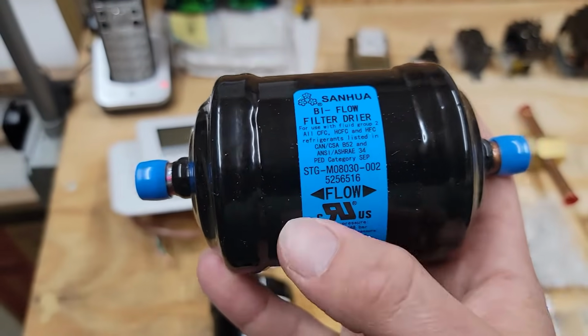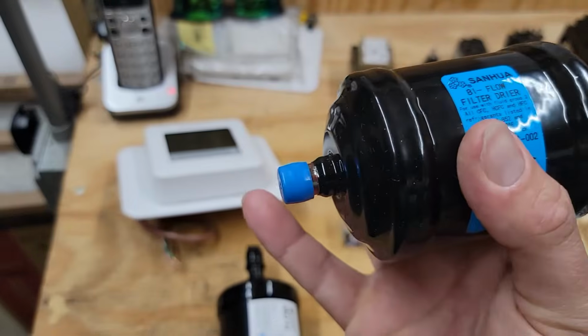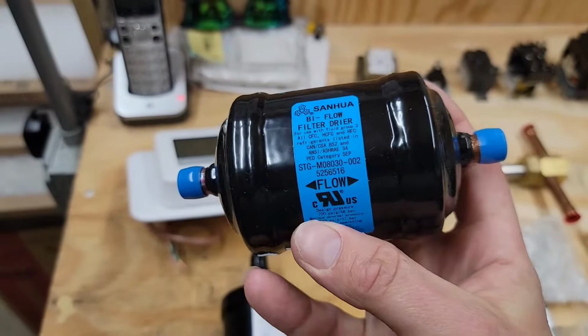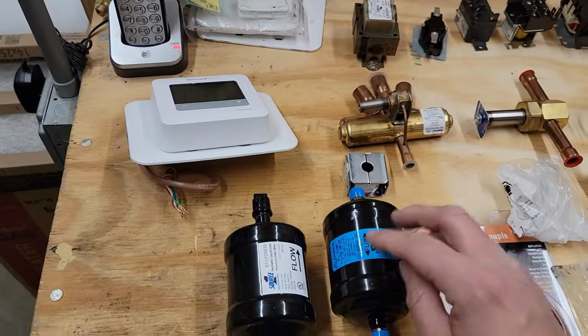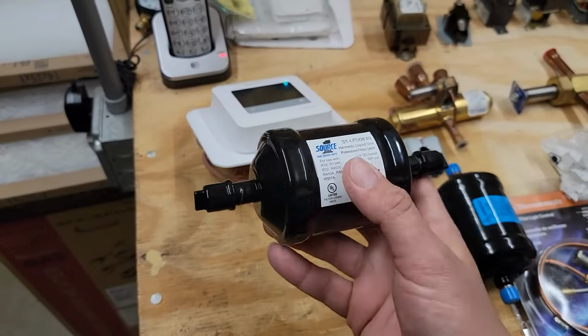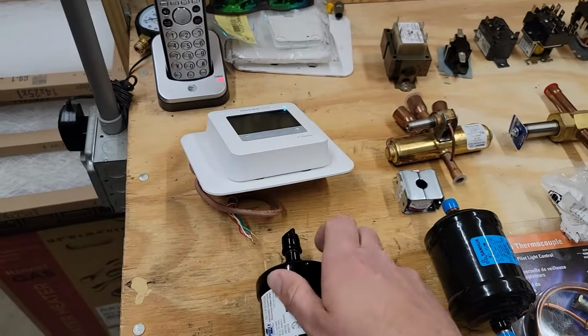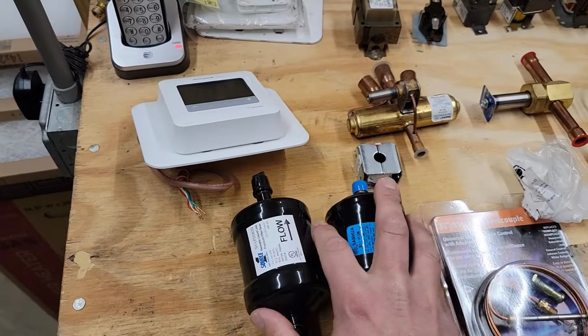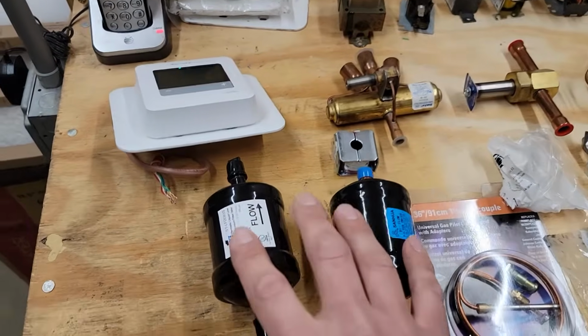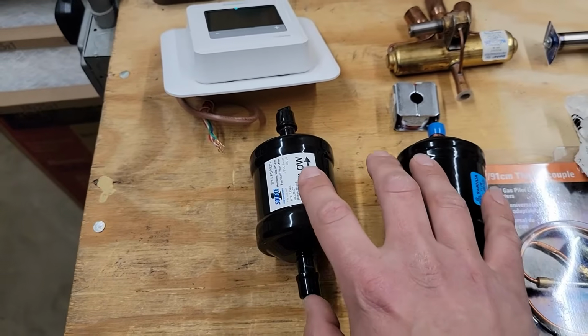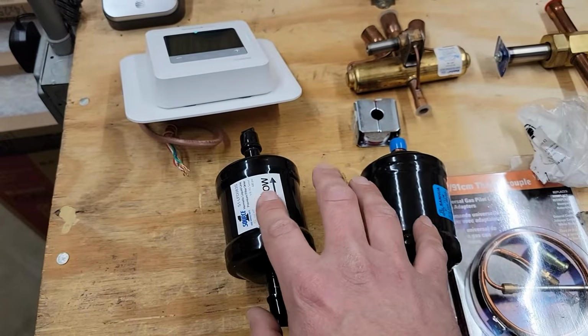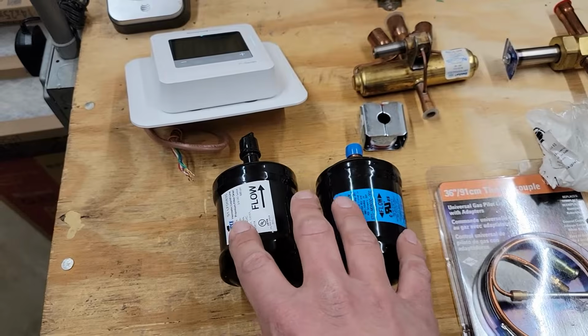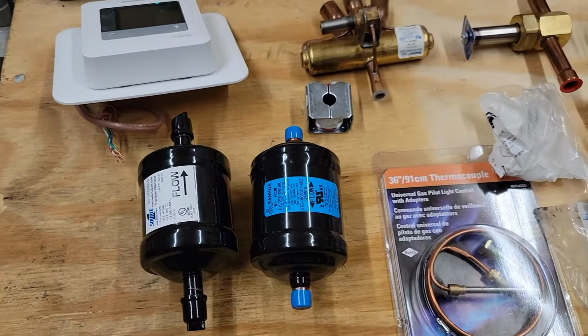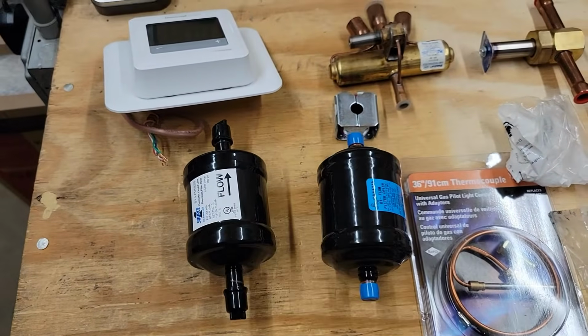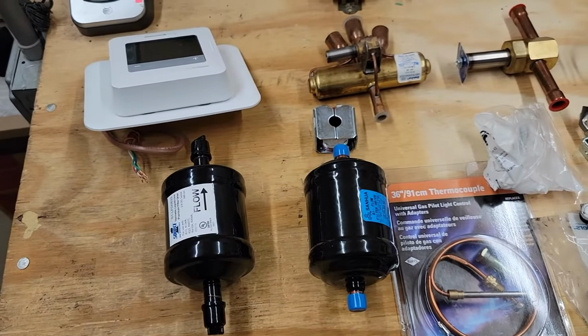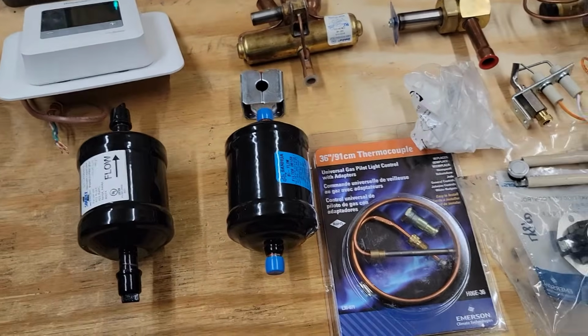How do we know? We have an arrow that points both directions. We've still got the 3/8 connections on each side for our copper, but this right here would be installed on a heat pump, and this would be installed on a split air conditioner, so just straight AC. And this is a way for you to ensure that your components like your compressor and your metering device don't have air or non-condensables in them or just debris. This right here is just a filter. So you definitely need to make sure that anytime you change a compressor, you change a filter dryer. Anytime you change anything in the system, you always go back with a new filter dryer.